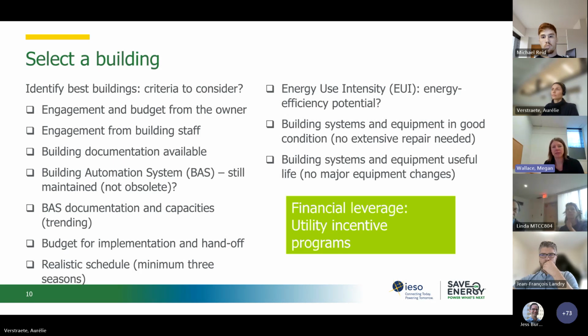When selecting a building, what criteria should you consider? How do you decide what's the best building for EBCx? Look at the engagement and available budget from the owner, the engagement from building staff, what building documentation is available, whether there's a building automation system (BAS), and if there is, is it still maintained and not obsolete? Consider the BAS documentation available and its capacities, such as trending, the budget for implementation and handoff, and whether a realistic schedule is possible—a minimum of 3 seasons is recommended.